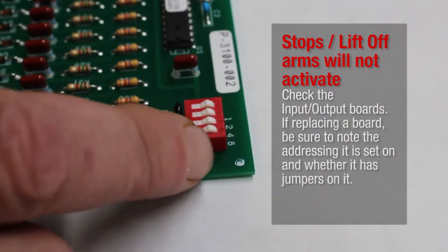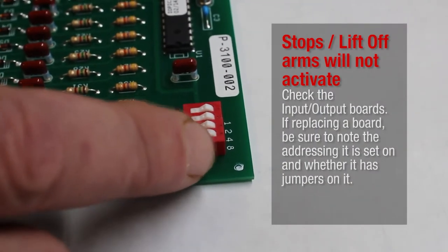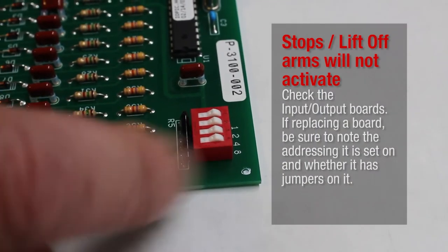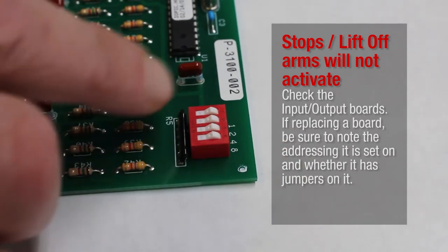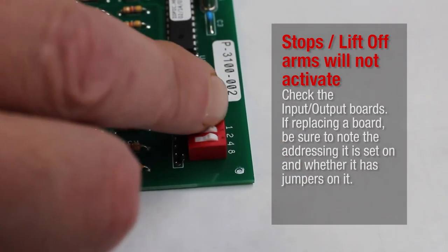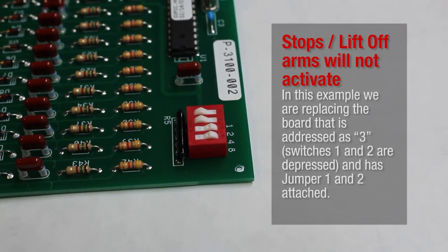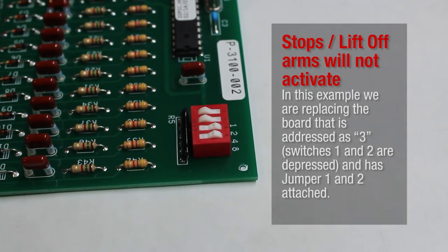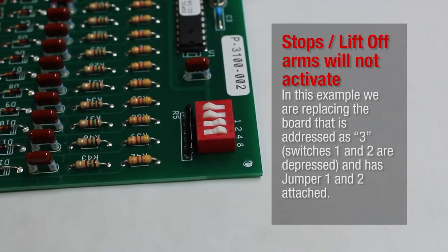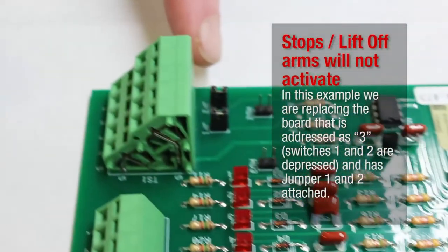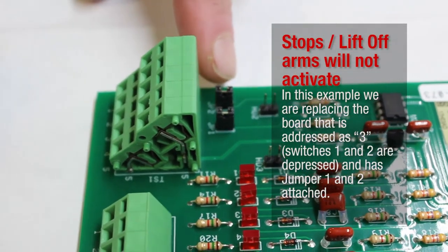Check the input-output boards. If replacing a board, be sure to note the addressing it is set on and whether it has jumpers on it. In this example, we are replacing the board that is addressed as 3. Switches 1 and 2 are depressed and it has jumpers 1 and 2 attached.